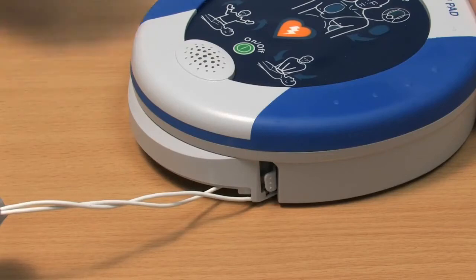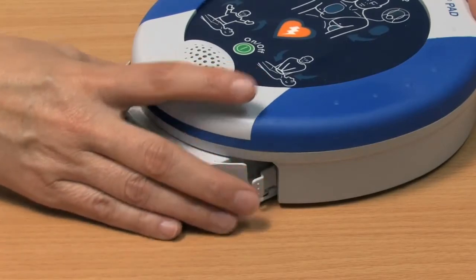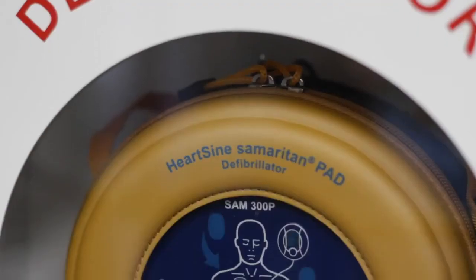After using the Samaritan PAD, contact your HeartSine channel partner to purchase a replacement pad pack. Slide a new pad pack into the unit and store it as usual. Remember to follow your local battery disposal guidelines.